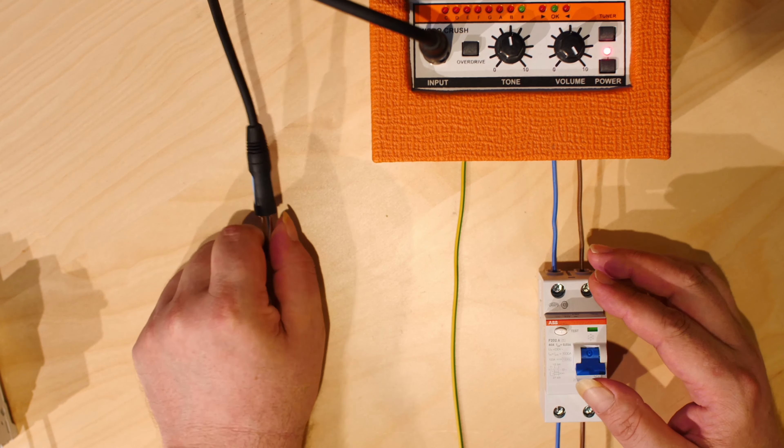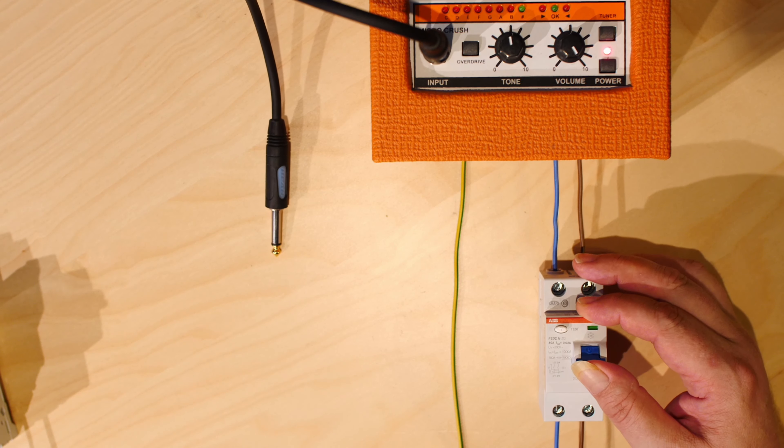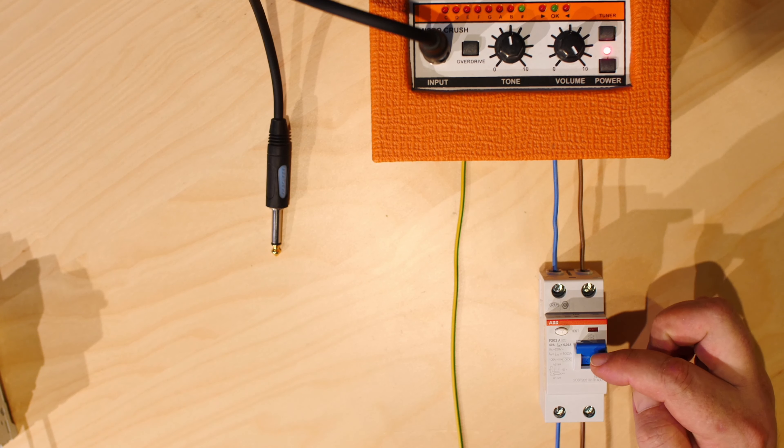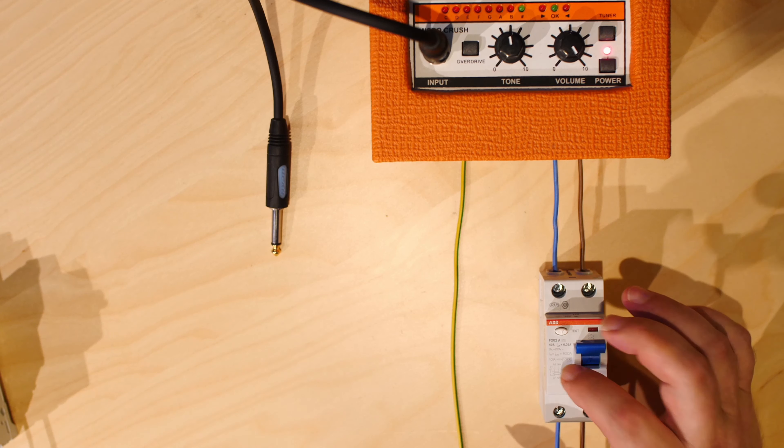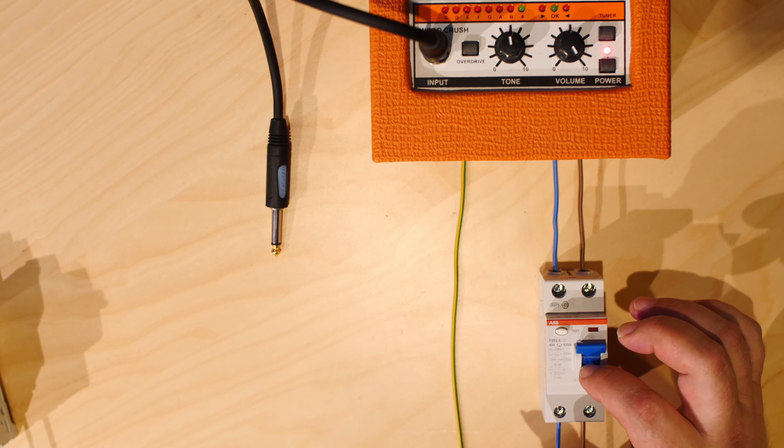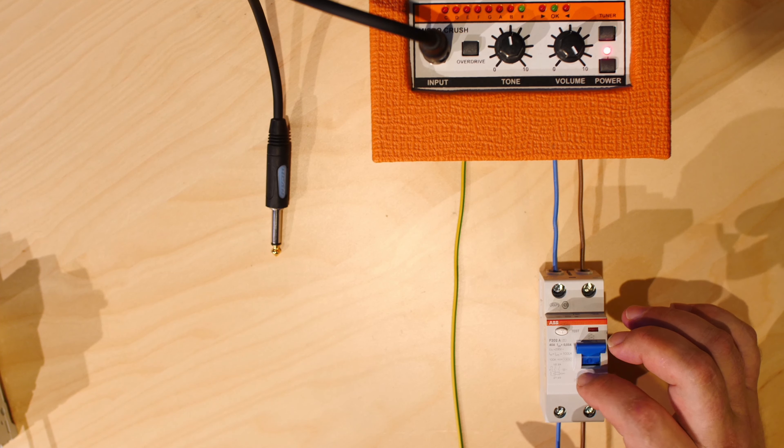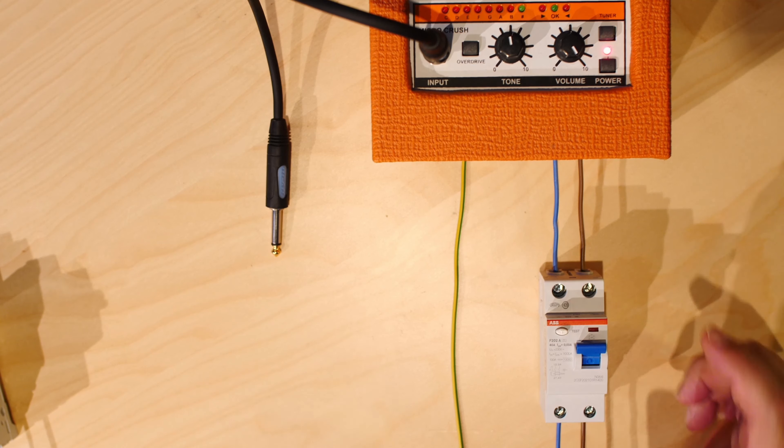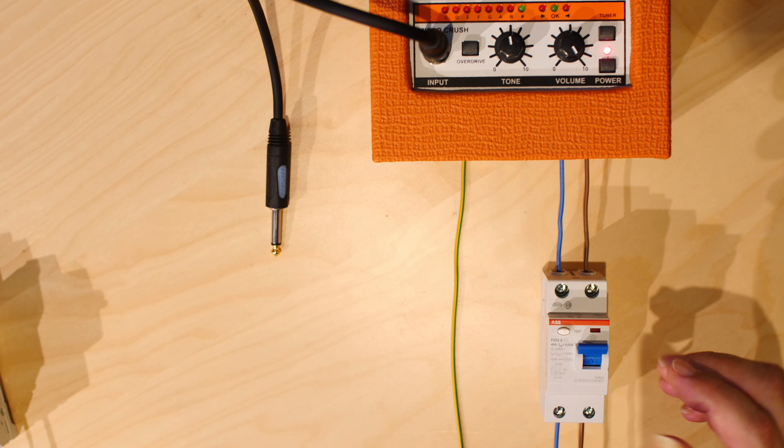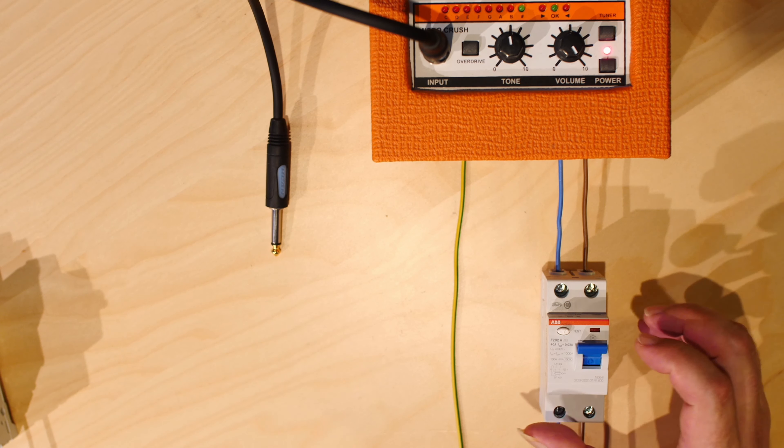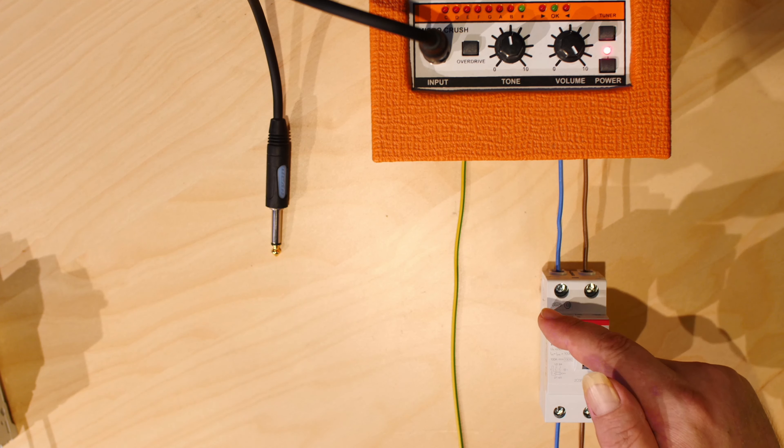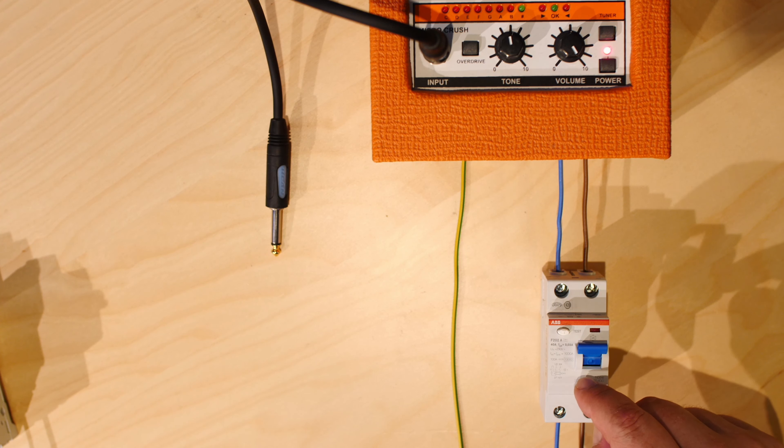And it will switch off at a difference of 30 milliamps. So, 0.03 amps it will already detect, and it will switch off within 0.1 seconds. So, it will switch off very fast. And this is the only device that will actually protect you, and your body, and your life. If you don't have an RCD, you are risking your life every single day. And not only in your house, in your electrical installation, this is made for electrical fixed installation inside a house, but there's also kind of wall plugs that include RCD device. And there's even a test button here, which you can press, and then it should immediately, bam, switch off. This is for testing, because this is what protects your life.